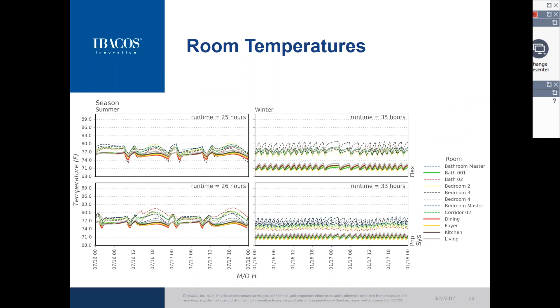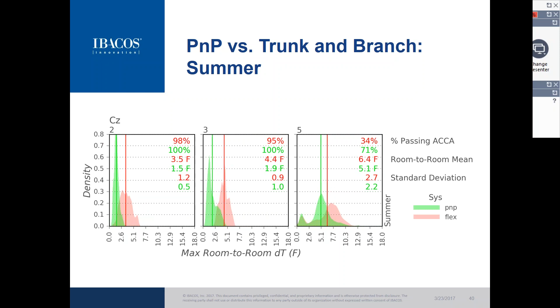That's primarily due to how we ran the design methodology. The dominating load was the cooling load in most of the rooms, meaning the number of ducts put in each room was typically controlled by the cooling load. When we ran the simulations, we didn't adjust the number of ducts for the winter months, so many rooms were receiving too much air in winter. Rooms with a very high cooling load, like south-facing and west-facing bedrooms, got way too much air in winter. So when we ran the simulation in winter with that single balancing of the ductwork, you see these higher delta T's.